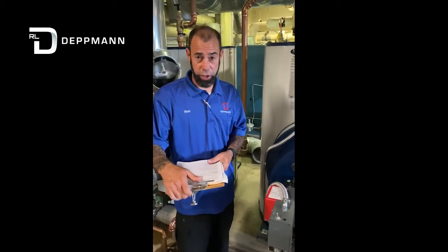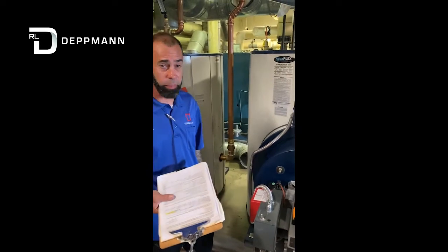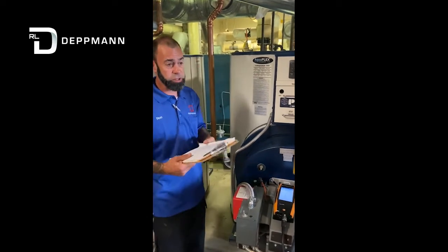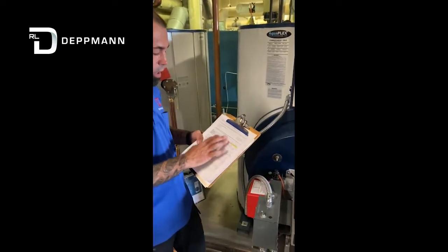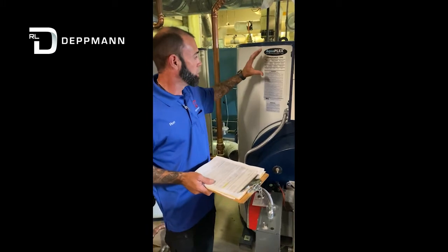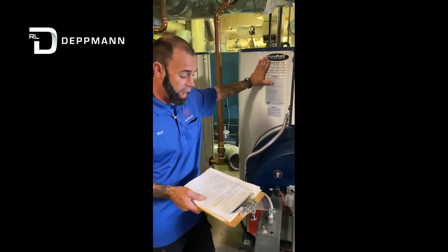Hey everyone, Ron Bonnick here today with the RL Deppmann Company. Today we're conducting a start-up on a PVI AquaPLEX gas water heater. First thing is you've got your start-up form — make sure you fill out all your start-up information. The first thing you're asked for is nameplate information off the water heater. Your tag is listed right here on the water heater — record all this information down.